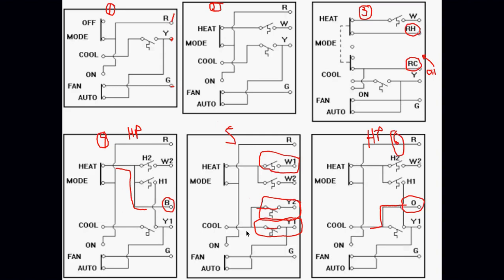Now, what terminal are all of these thermostats missing that might be important for a digital thermostat? There's one terminal missing on every one of these thermostats. Common. On all of these thermostats, you do not have a C. So on every single one of these thermostat subbases, if you see this, your thermostat either is not digital or it has batteries, okay? It does not have the common from the transformer on this thermostat, on any of these thermostats. So on all of these, if it's a digital thermostat, okay, you would have a C terminal as well, and this is where you start getting into a problem if you don't have enough wires in your thermostat.